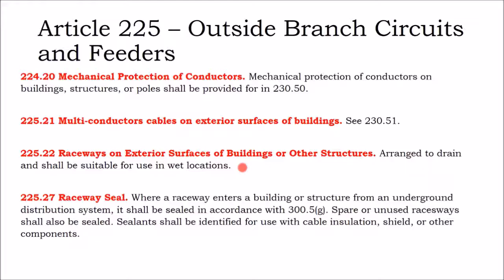And the contractor had not sealed the inside of the conduit. And so what happened was the water was pouring down into the box and actually getting up into the box. The fault was that while the pipe was in a pipe boot, the contractor did not put additional sealant between the pipe boot and the fitting inside the box. So water was getting into the box and then falling through the conduit into the attic. That was not arranged to drain. If we had instead taken that box and located it up to the top of the rooftop, you wouldn't get the water running down the edges of the conduit into the internals. So you have to think about drainage, and then again we've talked about raceway seals as well.